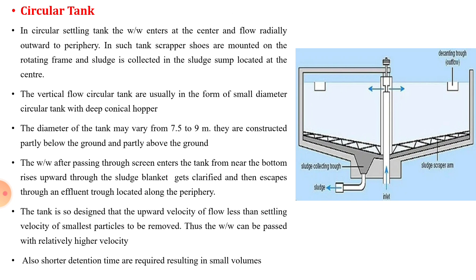Based on the shape of the tanks, it is classified as circular, rectangular, and hopper type. In the circular tank, the wastewater enters at the center and flows radially outward to the periphery. In such tanks, scraper shoes are mounted on the rotating frame and sludge is collected in the sludge sump located at the center. The vertical flow circular tanks are usually in the form of small diameter circular tanks with deep conical hopper. The diameter of the tank may vary from 7.5 to 9 meters. They are constructed partly below the ground and partly above the ground.